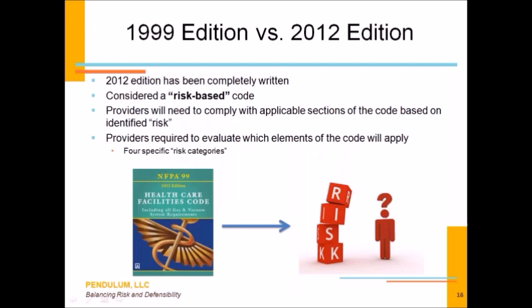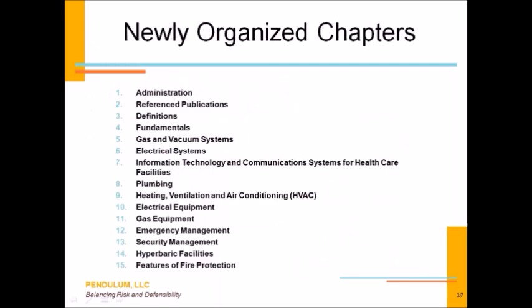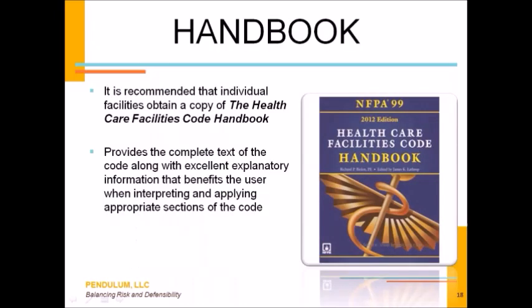In the 2012 edition of NFPA 99, everyone on the line today needs to know that it is a risk-based code. And because it's a risk-based code, it applies to healthcare facilities in accordance with the identified risk. When it comes to identifying the risks, there's a process that we're going to talk about. But before we get there, if you're someone, especially in a hospital, an accredited facility, you need to understand that in those facilities, the code itself is completely reorganized. If you took the 1999 edition and weighed it against the 2012 edition, you're going to see that everything has been reorganized in a completely different manner.